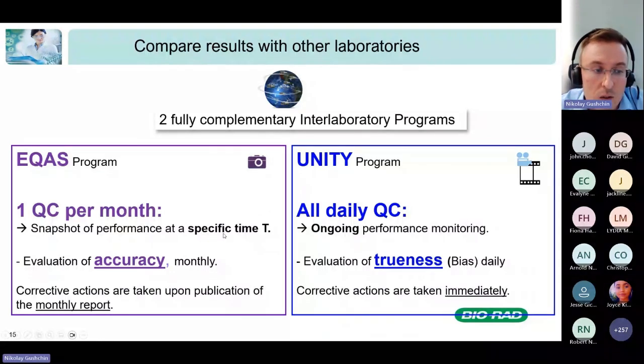So it's retrospective analysis. You always have the report with some delay, a little bit later, like 3 days later, for example. And this is evaluation of the accuracy. In the Unity program, you have much more data because you have the data from all your daily QC, all your daily measurements from every day. And this gives you the ongoing performance monitoring. And this is called evaluation of the trueness or bias.